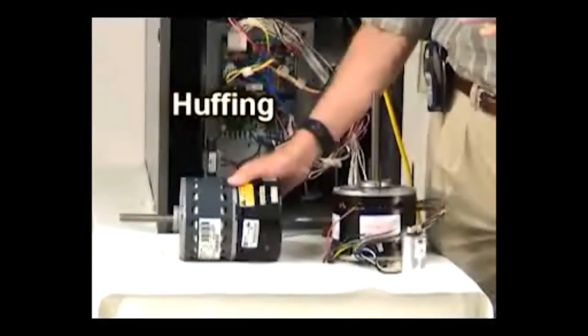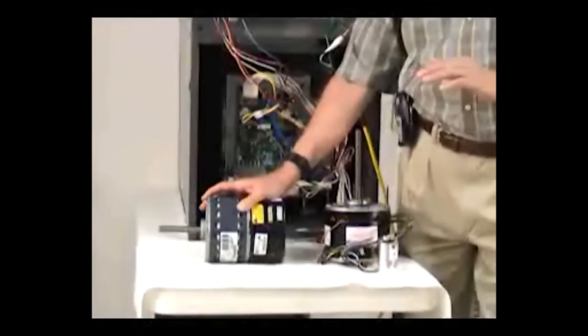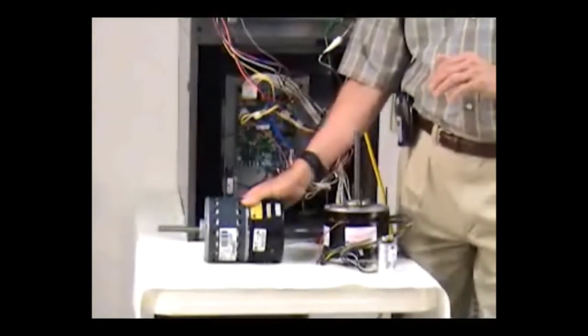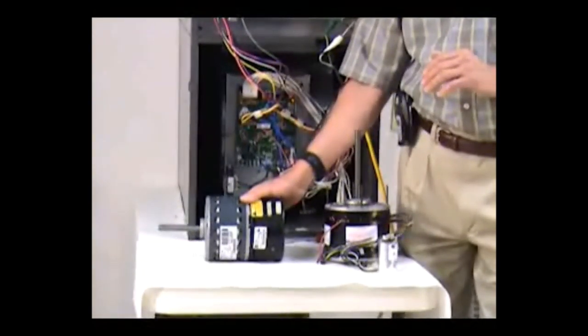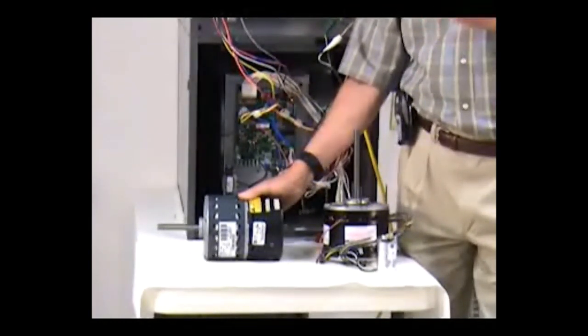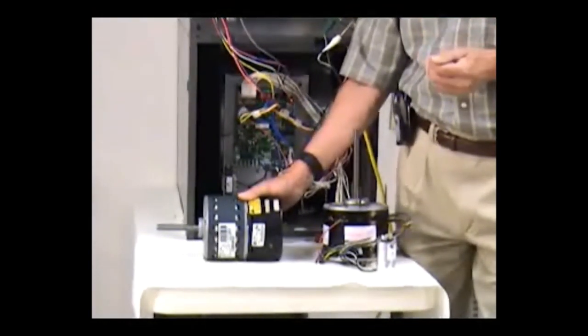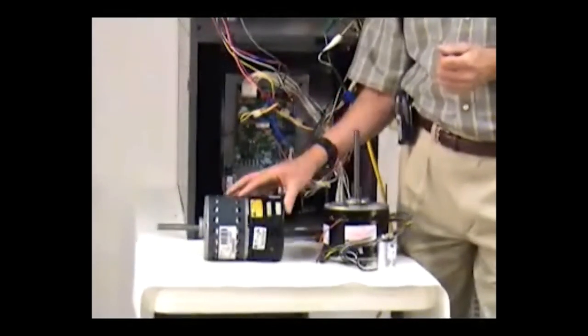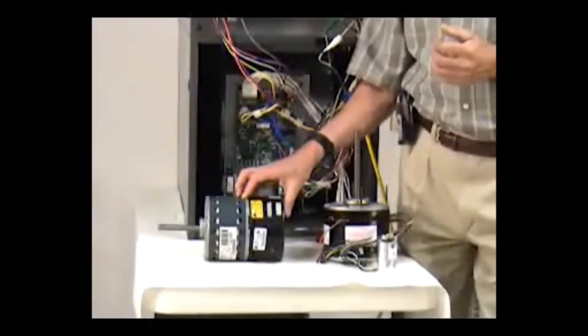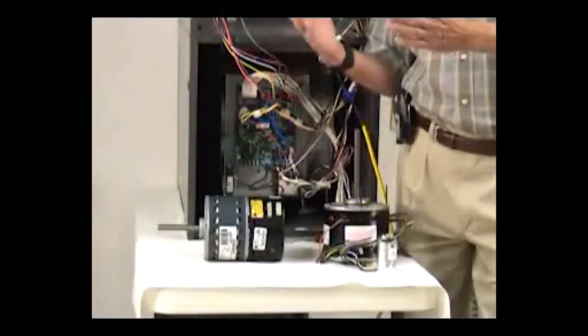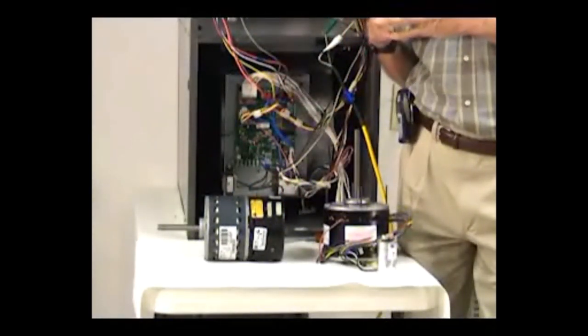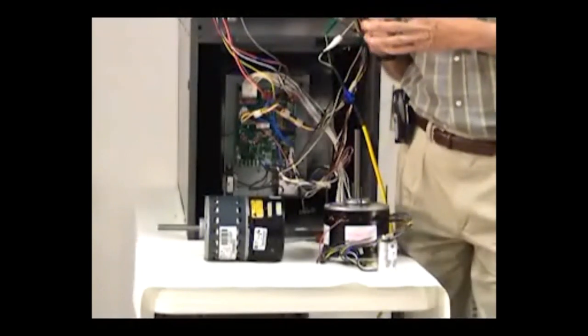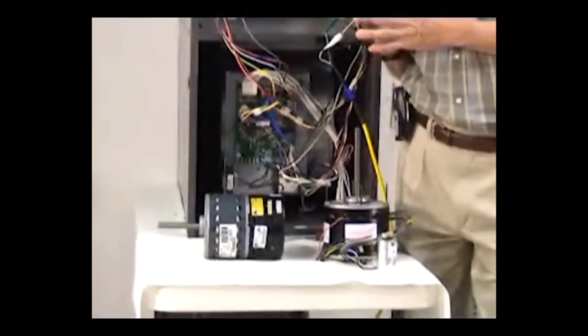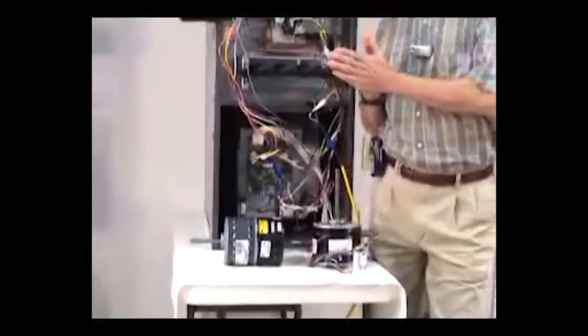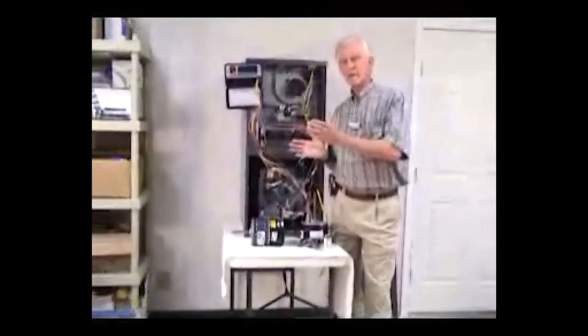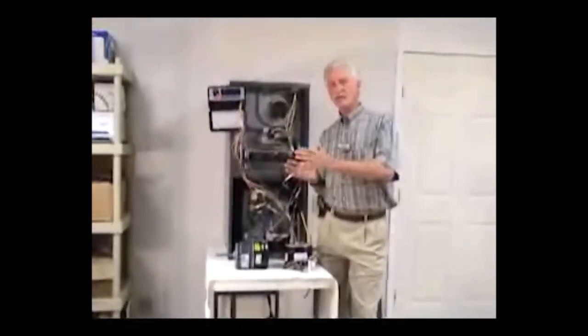The off side of anything that we have talked about would be that if you exceed 1 inch in static, if your static pressures go to that point, you can have a situation where you get into what the manufacturers call huffing. Huffing would be a case where this motor has reached those ranges at which it is no longer able to cope with the situation that it has. Typically, external static pressures are way too high, and the motor will actually back off in RPM and then increase its RPM. Back off and increase.